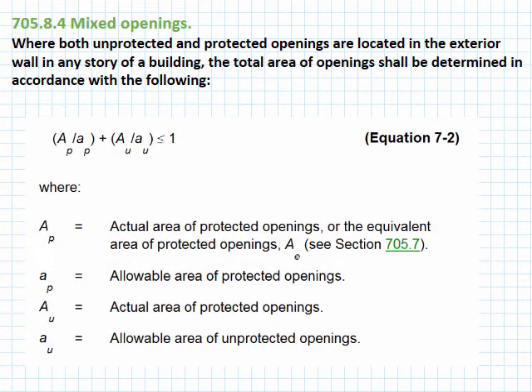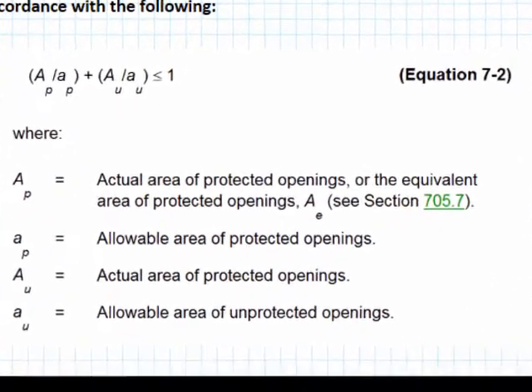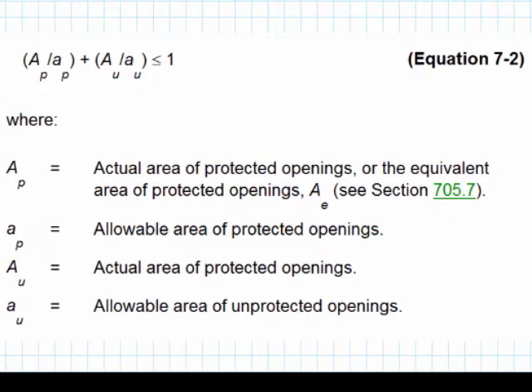Where an exterior wall on any story has both protected and unprotected openings, the unity formula as set forth in Section 705.8.4 determines the maximum areas of the openings. The simple explanation of Equation 7-2 is that if a percentage of the protected openings is utilized on an exterior wall of a story, then the remaining percentage is the total area permitted for unprotected openings.